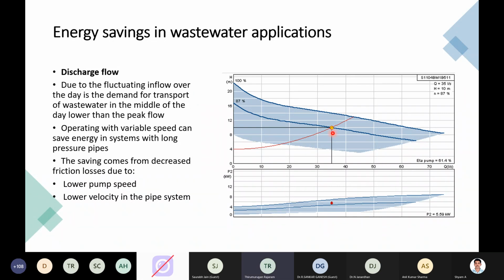So here you can find the 100% duty, you are able to reduce to 87% of your frequency, and obviously that will impact your energy saving on your wastewater applications. So two things: the pump speed will come down, and second, you will have a much lower velocity in the pipe. That also increases the life of your pump and the life of your pipes.